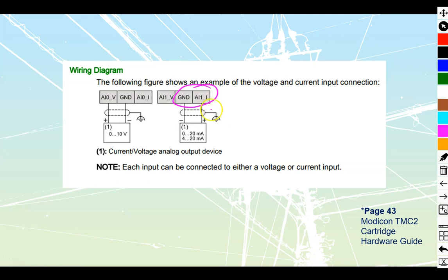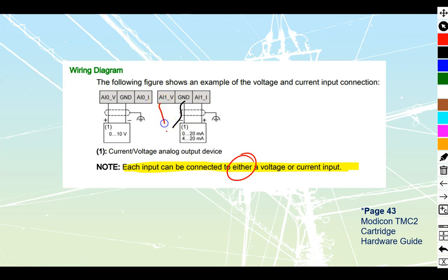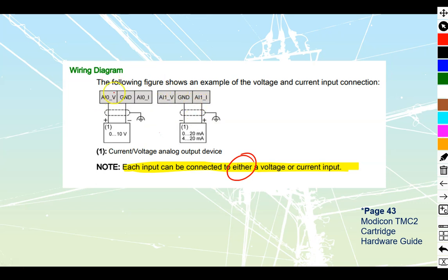You need to note that each voltage or input can be connected to either a voltage or a current input—you cannot do both. In other words, I could not take another ground down and a 0 to 10 volt signal at the same time. It simply will not work. You have to select one or the other, so no more than two inputs per card even though you see two voltage inputs and two current inputs.